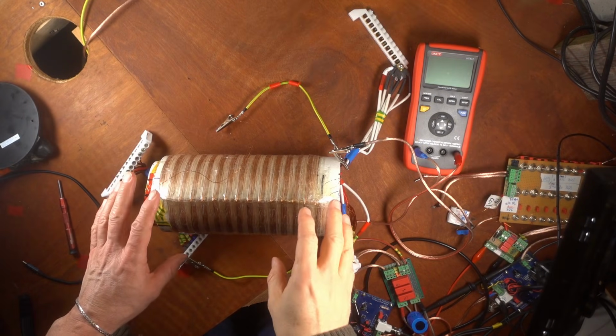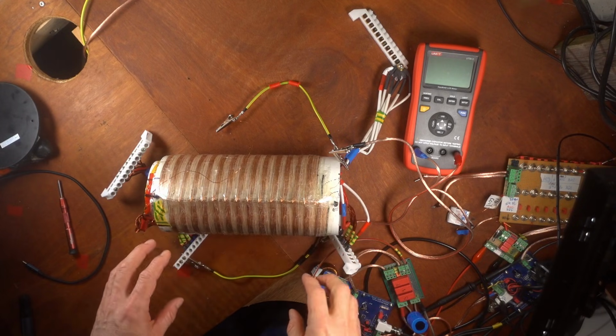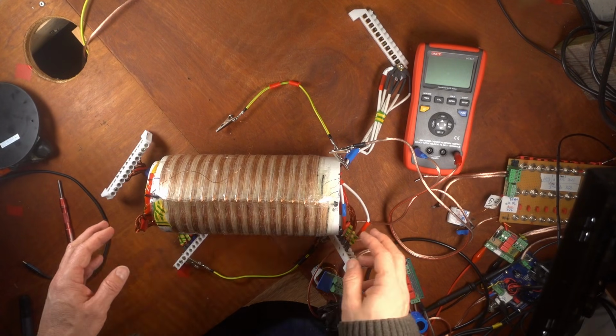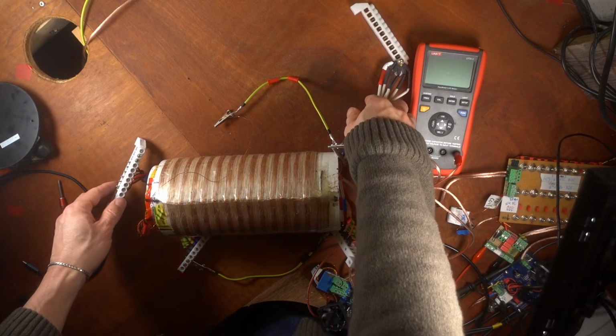Okay, I shorted out the high voltage coil and I shorted out the high current coil and I open-ended the middle coil. And I now measure 296.8 picofarads of capacitance between those two coils that are nested inside each other. And the middle coil is just floating. It's not playing any role.